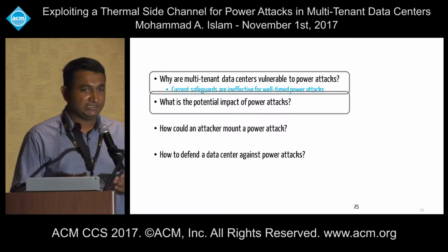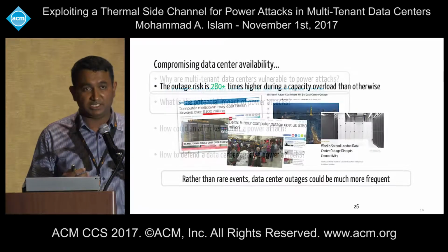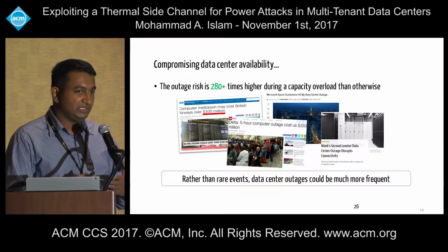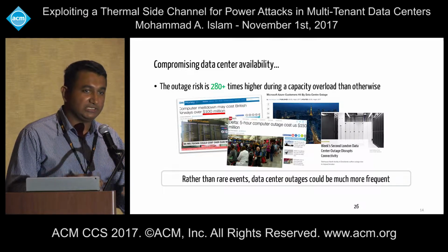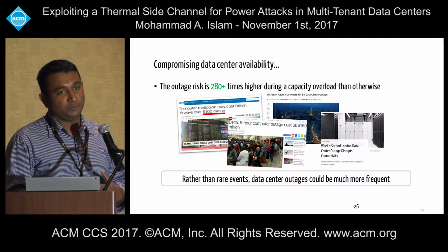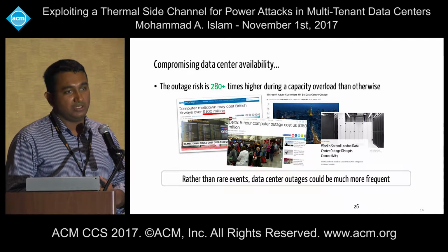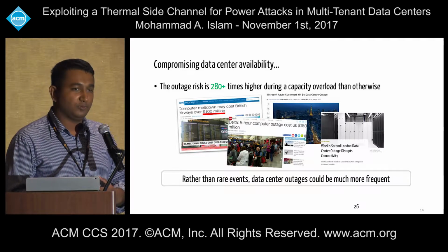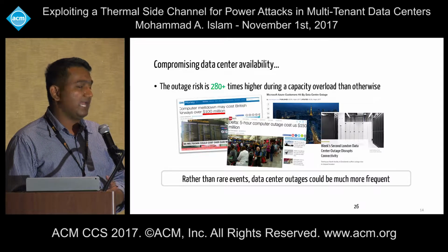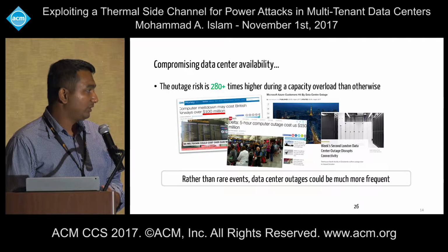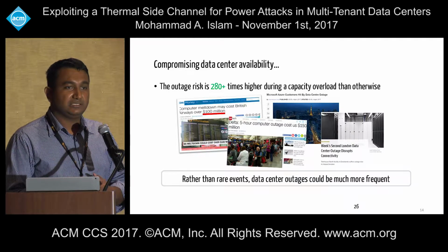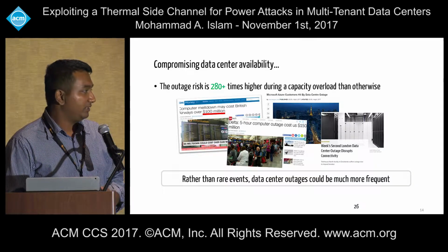The immediate impact, as we discussed, is the overload of the system capacity. What the overload does to the data center is increase the outage probability. In our estimate, it increases the outage probability almost by 280 times compared to without any overload. As a result, this power outage, which is supposed to be a very rare event, can become frequent.